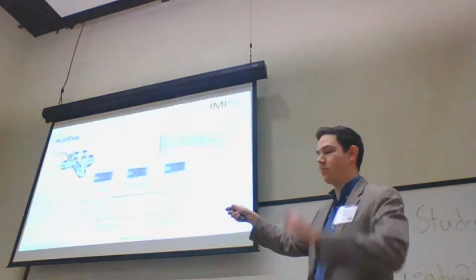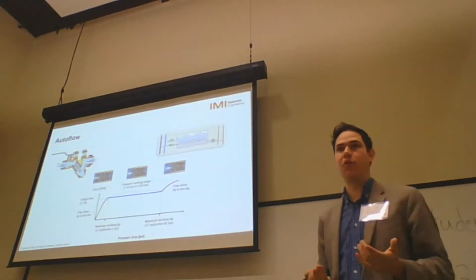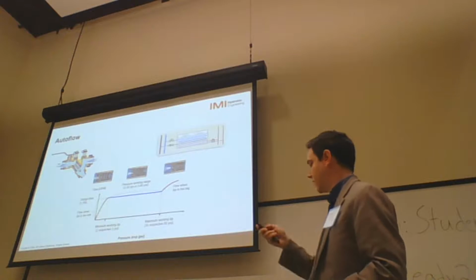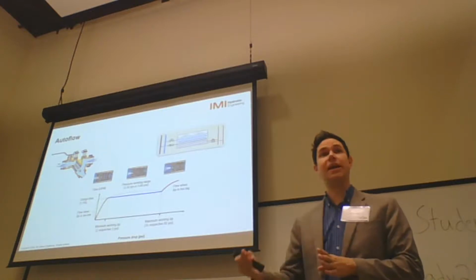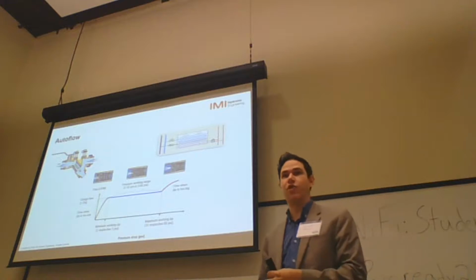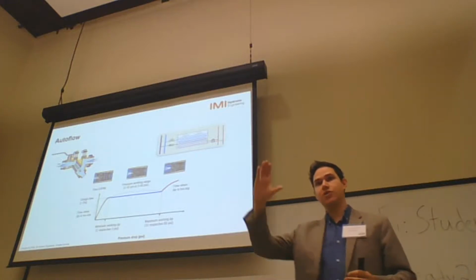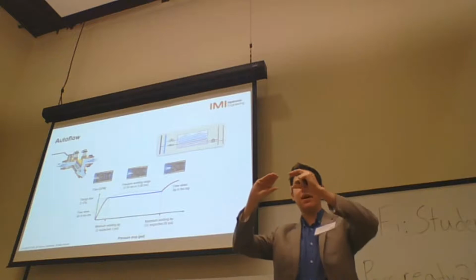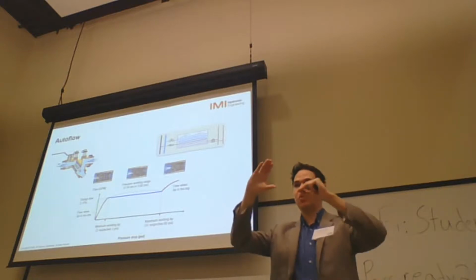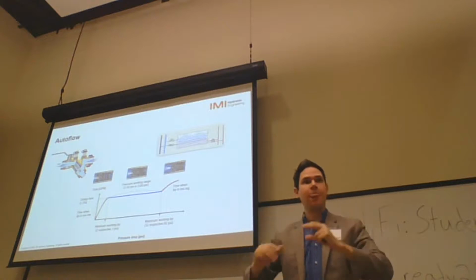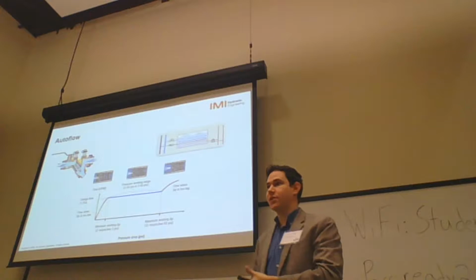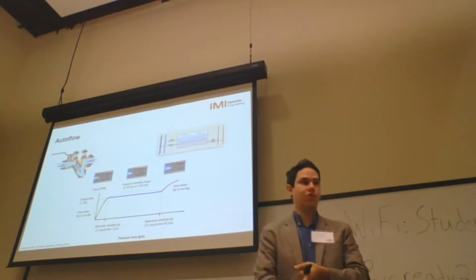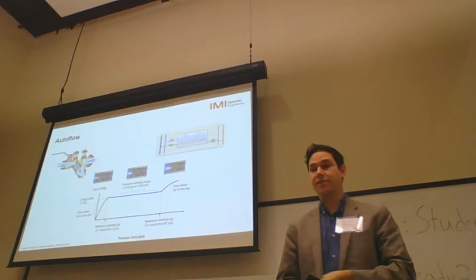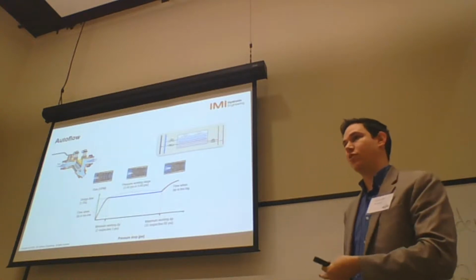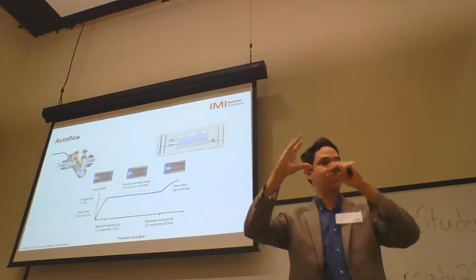And basically it is a cartridge that goes inside the valve and keeps opening and closing to keep a constant flow, also known as a flow limiting device. It is not recommended for installations with modulating control valves, because if you have a modulating control valve and an automatic balancing valve on the same coil, as soon as the modulating control valve starts closing, the automatic balancing valve will open up at the same time. So they'll basically be fighting against each other. An automatic balancing valve or flow limiting device is always recommended for on-off applications, water source heat pumps, and in many cases cooling towers as well, but never with a modulating control valve, because they'll be fighting against each other.